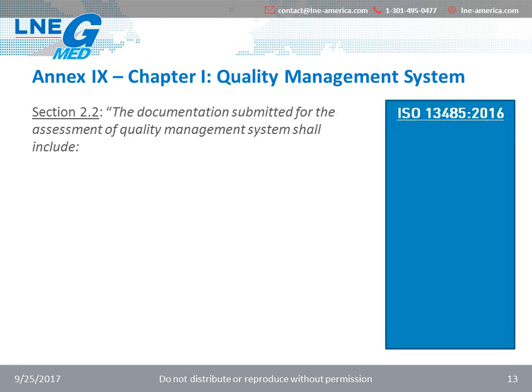Section 2.2 of the regulation is also very prescriptive and clearly mentions what the documentation that is submitted for conformity assessment needs to contain. These include the manufacturer quality objective. This quality objective is also a notion that you find in section 4.2.1 of the ISO 13485:2016, where it has to be documented for the QMS.